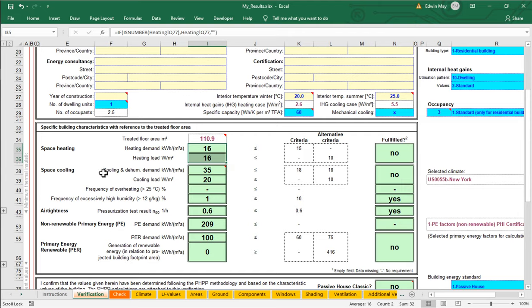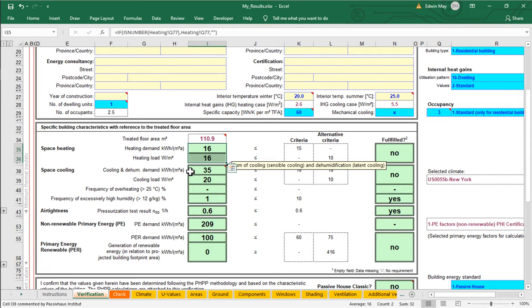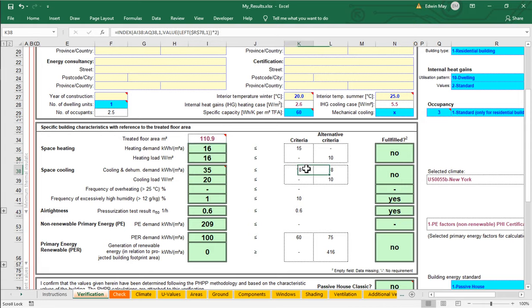But notice here that the cooling and dehumidification demand is very high. We're up at 35 right now and we have a target of 18 kilowatt hours per square meter per year. We're really high. We need to figure out what it is that's driving that cooling and dehumidification demand so much.